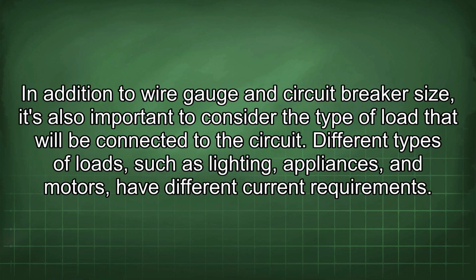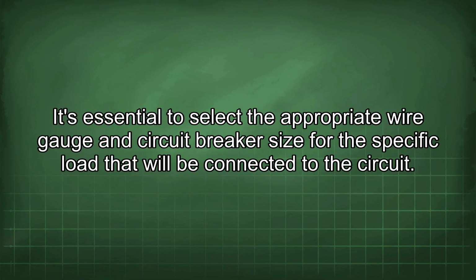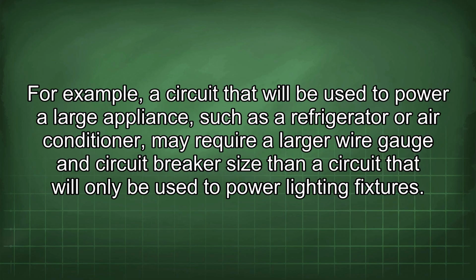In addition to wire gauge and circuit breaker size, it's also important to consider the type of load that will be connected to the circuit. Different types of loads, such as lighting, appliances, and motors, have different current requirements. It's essential to select the appropriate wire gauge and circuit breaker size for the specific load that will be connected to the circuit. For example, a circuit that will be used to power a large appliance, such as a refrigerator or air conditioner, may require a larger wire gauge and circuit breaker size than a circuit that will only be used to power lighting fixtures.